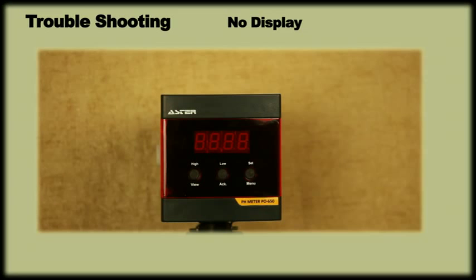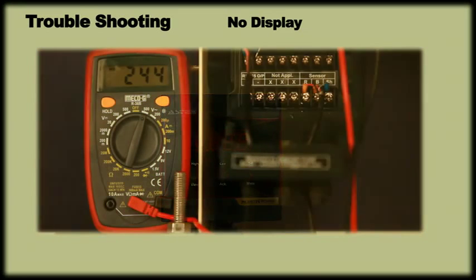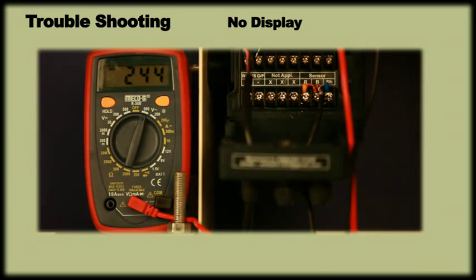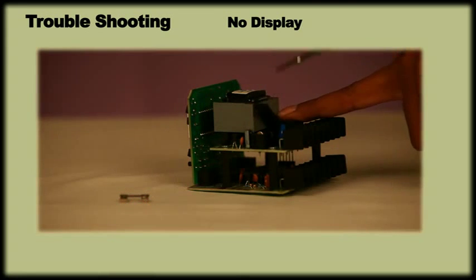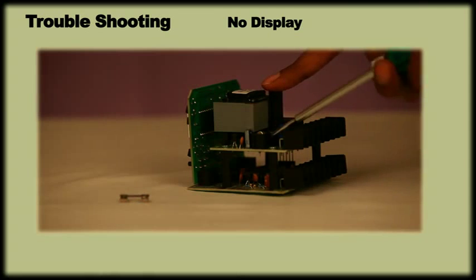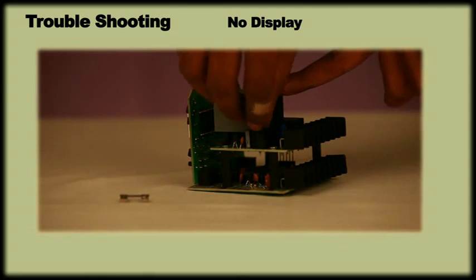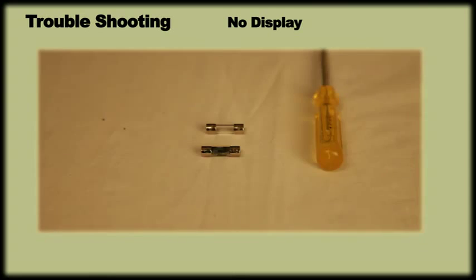Troubleshooting. If the meter shows no display, check the input supply with the help of multimeter and ensure it gets required supply. In case display remains off despite proper supply, open the instrument and change the fuse with a new 630 mA fuse.